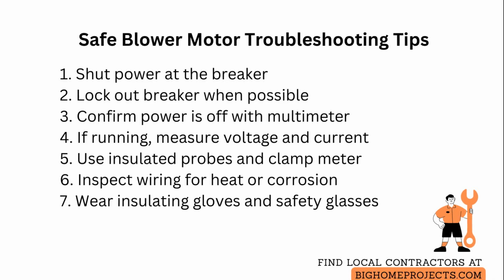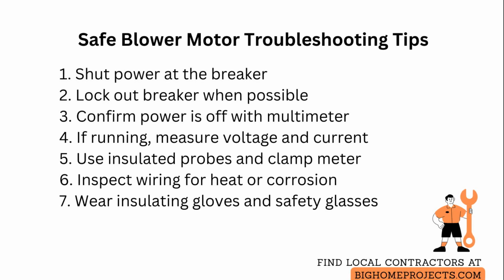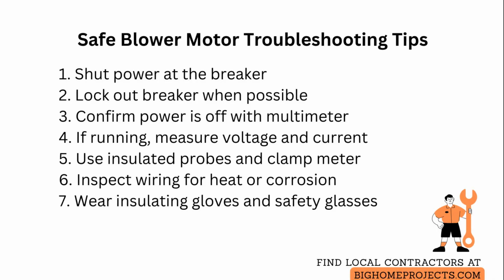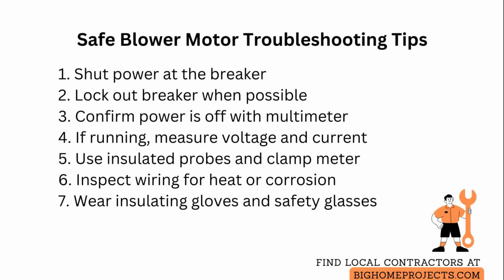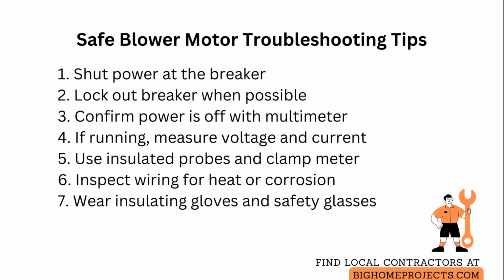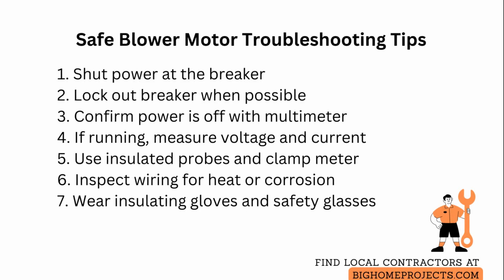If the motor must run for a diagnostic test, measure voltage and current from a safe distance using insulated probes and a clamp meter or true root mean square meter when required. Inspect motor wiring and connectors for heat discoloration, melting, or corrosion, because those signs point to high resistance connections that can cause arcing and failure.